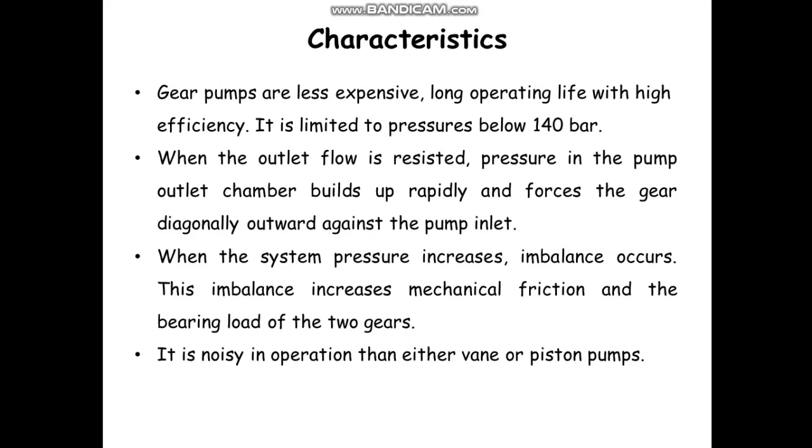So when the outlet flow is restricted or resisted, then the pressure in the pump outlet chamber builds up rapidly, and that forces the gear diagonally outward against the pump inlet. So this shows that the resistance to the flow creates the pressure, not just the pump. So when the system pressure increases, an imbalance occurs, and to avoid this imbalance, we need a pressure relief valve, because this imbalance increases mechanical friction, and that may harm the bearings of the two gears.